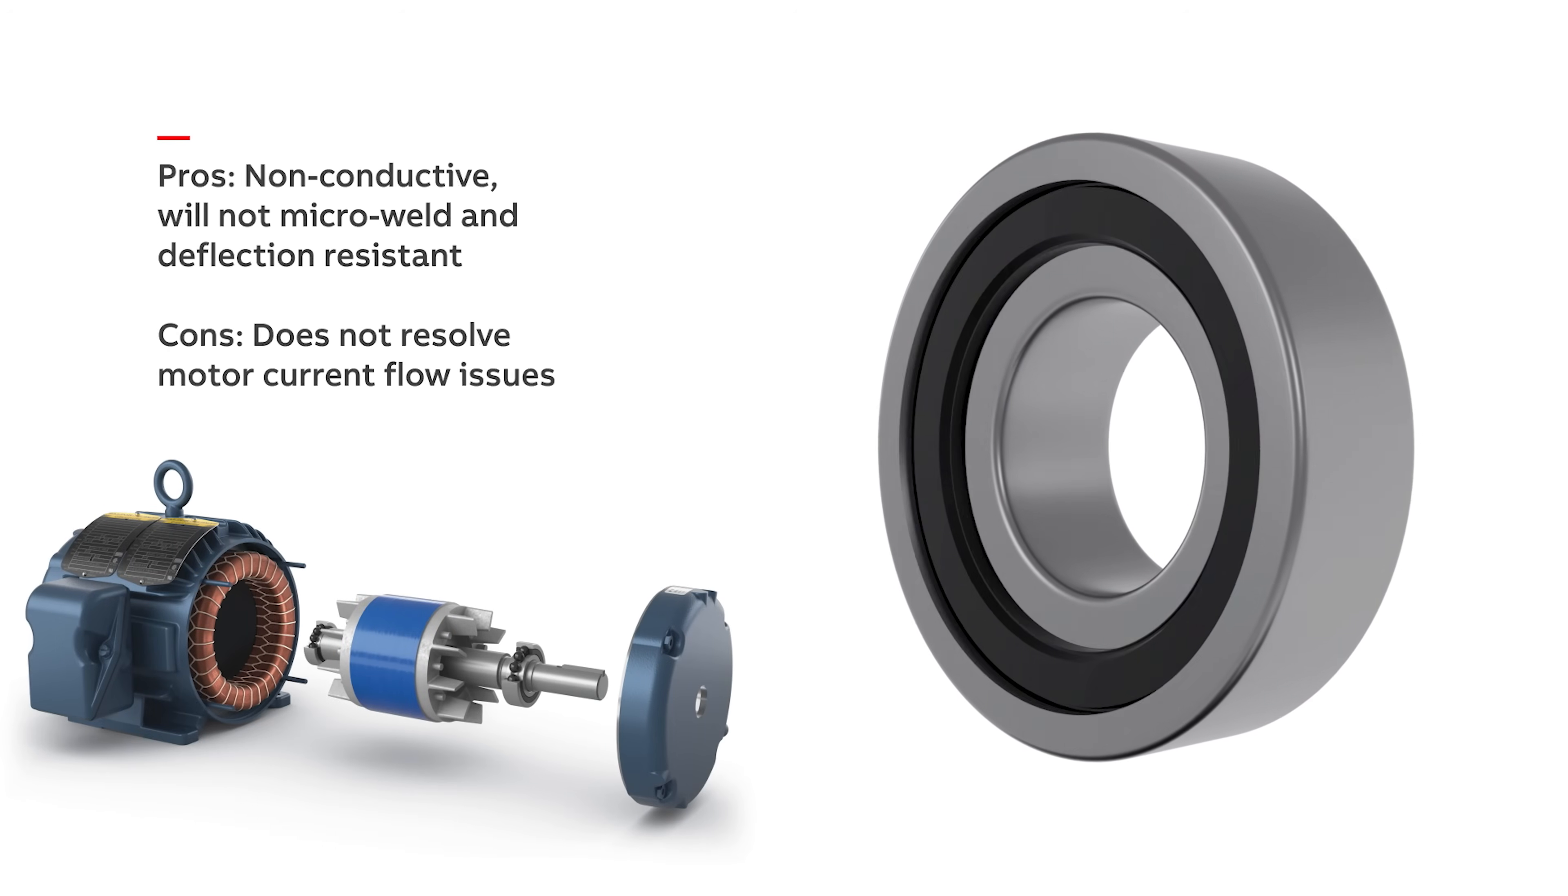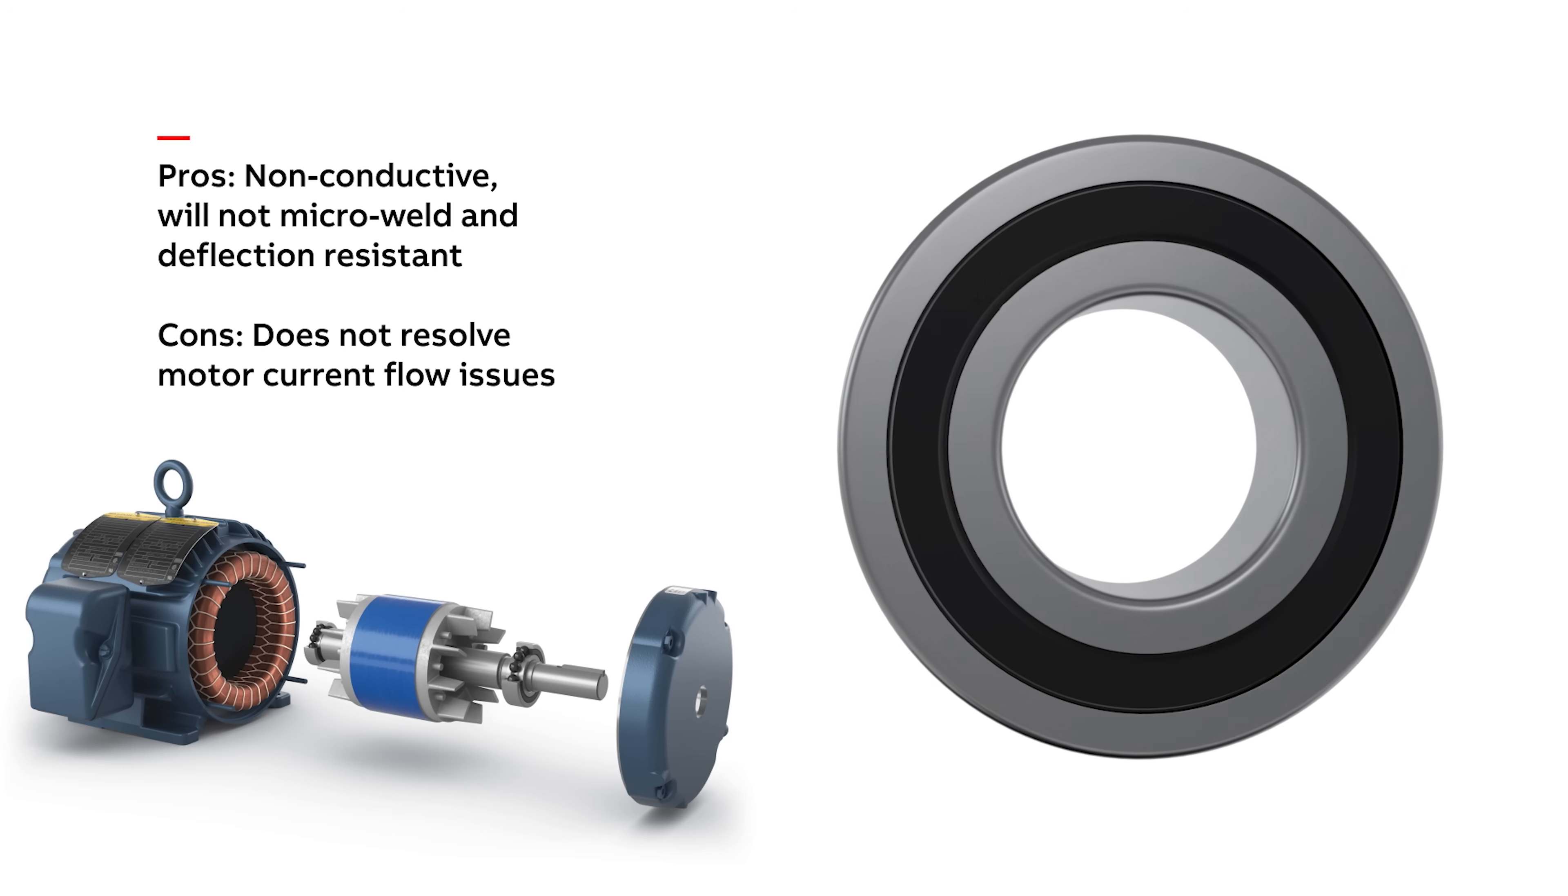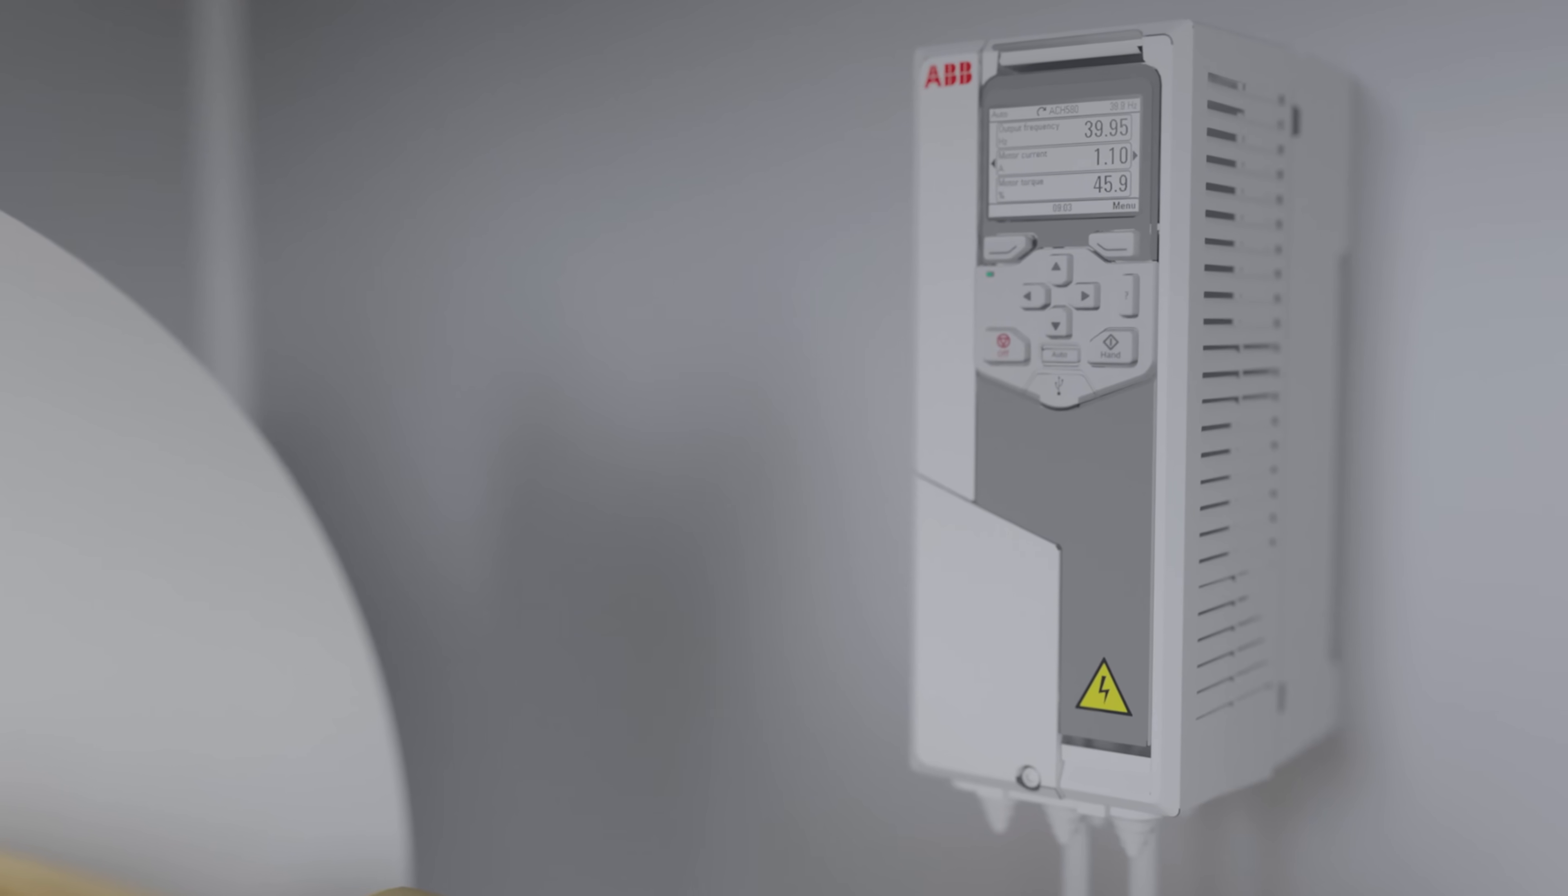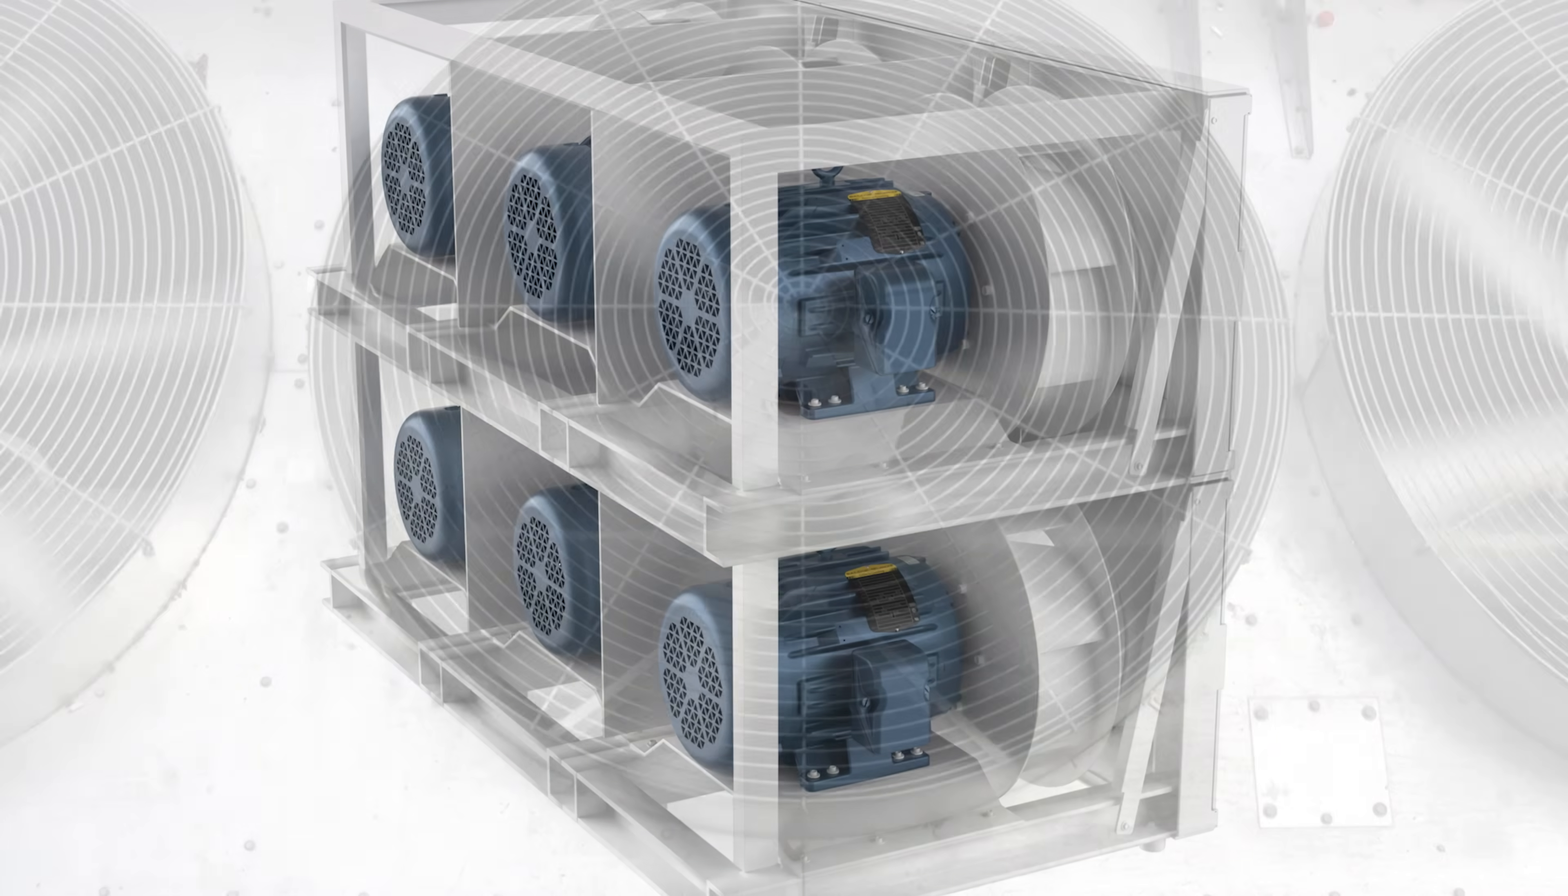However, the current will seek a path to ground, which means it will most likely travel through the driven equipment. Since ceramic bearings will not remove the current from the rotor, only specific applications, such as direct drives or equipment utilizing non-conductive couplings, are recommended for motors with ceramic bearings.